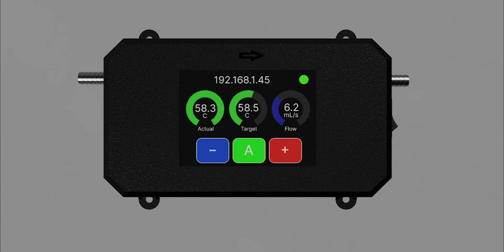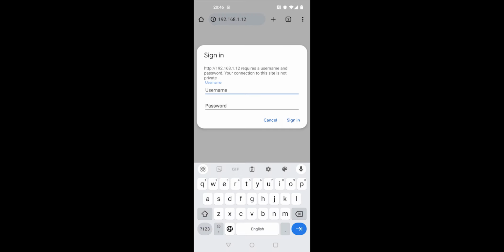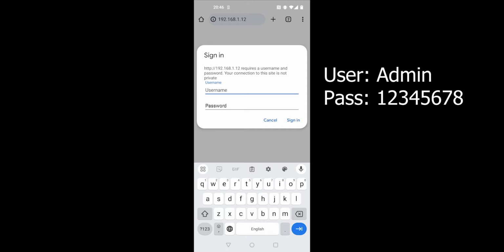Everything past this, we will focus on the web interface. This is where you get the ability to remotely monitor ATACC, modify its behavior, and make it perform tailor-made just for your specific setup. To get started, you simply need to type the address located on the touchscreen into any web browser. Note, you will not get an address unless ATACC is connected to Wi-Fi. Once the address is typed in, you will be prompted to log in. The default username is admin, and the default password is 1 through 8. Once logged in, you will have free reign over the web panel.